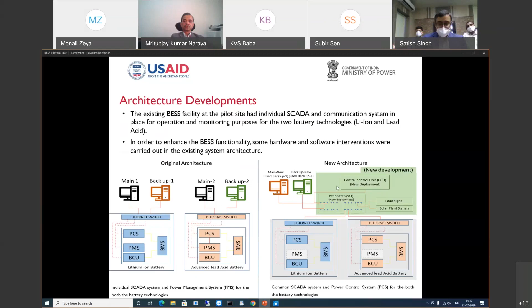So earlier the system was capturing grid frequency. However, we also need to capture the load of a particular feeder, which will be our grid feeder. Similarly, we also got the inputs from the solar rooftop plants to see how PV smoothing can be performed. Now, key interventions under the pilot included deployment of a new controller, as I told earlier, hardware switches, then software updates of the existing SCADA system. So all these were part of the grantee KC International's scope, which they deployed on site here.